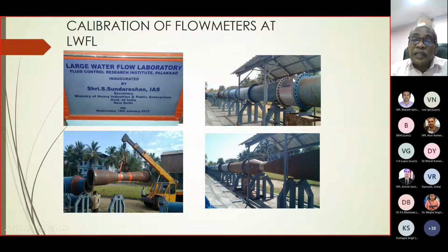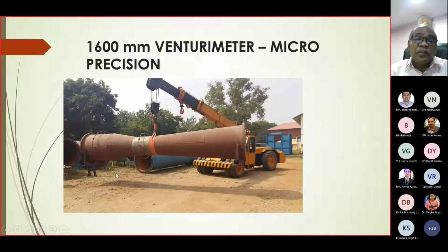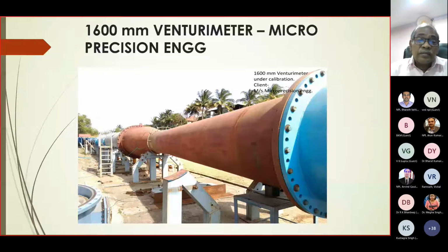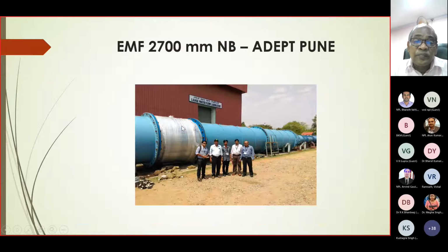See, this is a 900 mm electromagnetic flow meter. This is now a 1200 mm electromagnetic, this venturi meter. This is a 1600 mm venturi meter. See, micro precision. This is a 1600 mm venturi flow meter. You cannot calibrate it anywhere in India. So now we have this facility, the large water flow facility. So this is another view of the 1600 mm venturi meter.